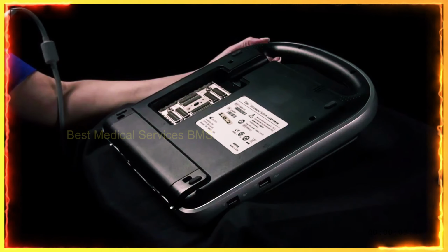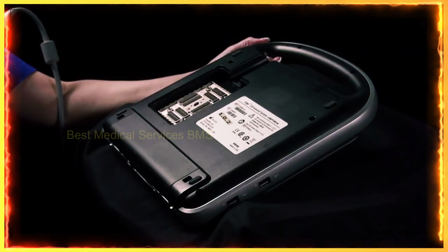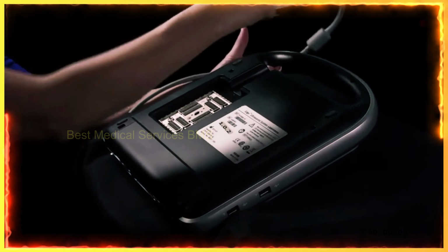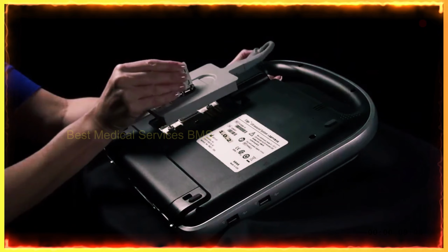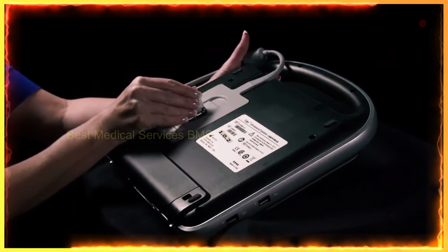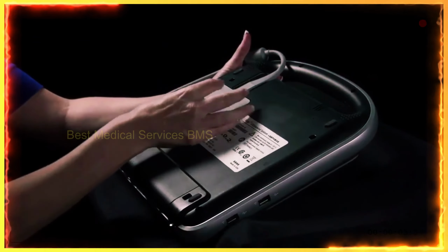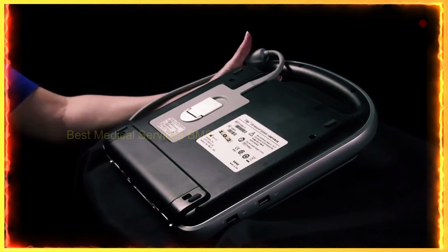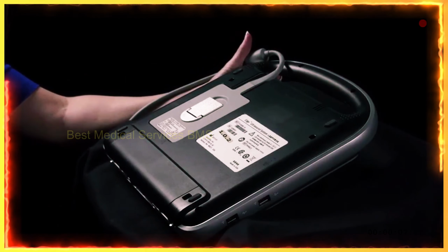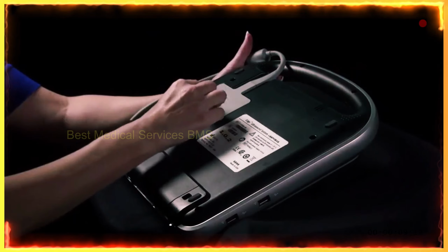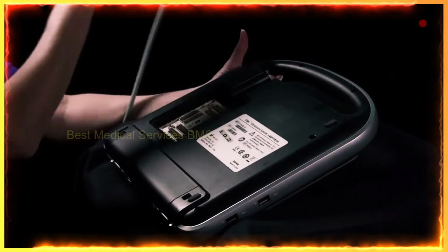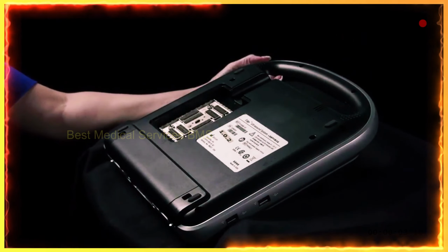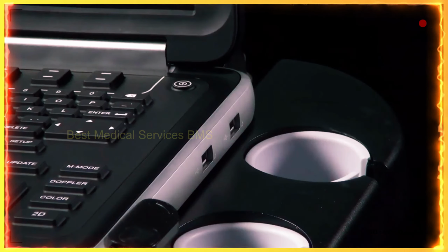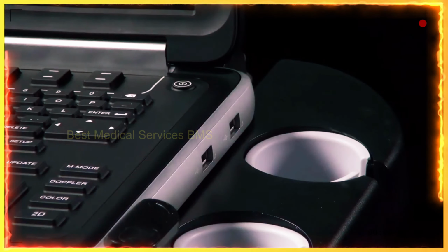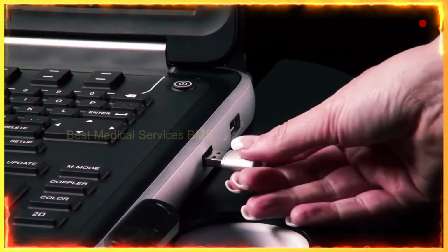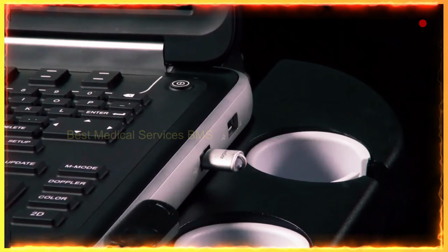To connect a transducer, turn the system upside down. Pull the transducer latch up and rotate it clockwise. Insert the transducer connector, turn the latch counterclockwise, and press the latch down. To remove the transducer, pull the latch up and rotate it clockwise. Pull the transducer connector away from the system. On the right side of the system, there are ports for USB devices. These can be used for image storage and system software upgrades.